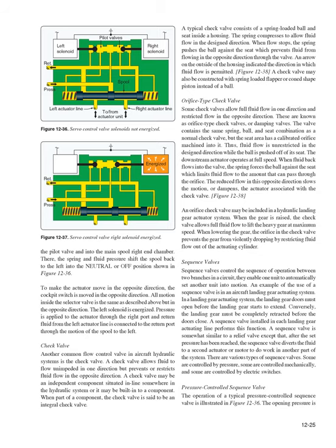The left solenoid is energized. Pressure is applied to the actuator through the right port, and return fluid from the left actuator line is connected to the return port through the motion of the spool to the left.